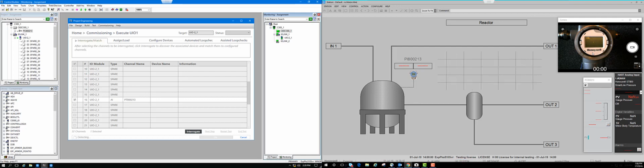So right now that service that's running, that HART service, is saying, okay, on this channel 16 I have whatever the respective name is that comes through, and that is what will show up here in the device name column. Okay, the expected is PT800-213. That's what I configured on my project side. That's what I'm expecting here, and sure enough, it did find PT800-213. Okay, so now I know I have the instrument tied to the right strategy. So now I can go ahead and assign and load the instrument to that control strategy. As you can see, it's loaded, server load complete, and then it's going to bring it onto my monitoring side where I can go ahead and configure the device to the system and start the loop test, which is pretty awesome. You'll see it here.